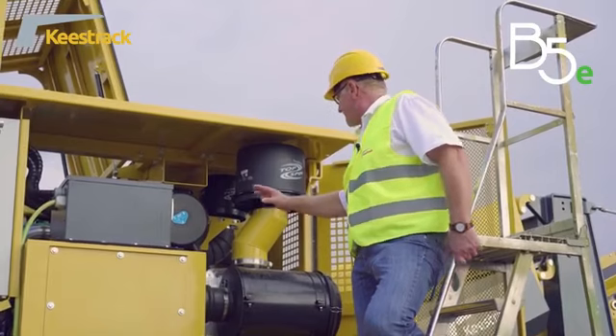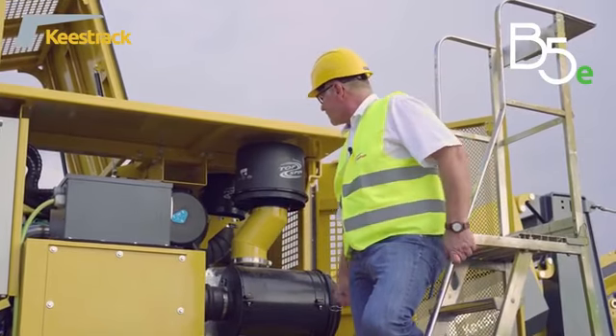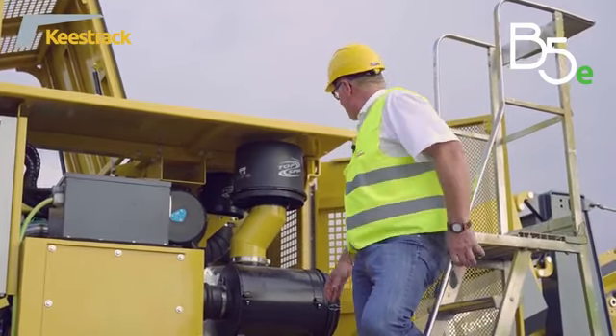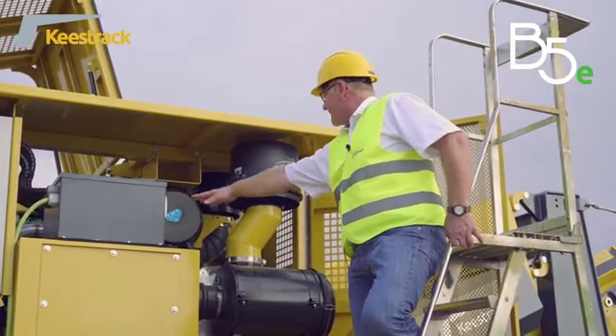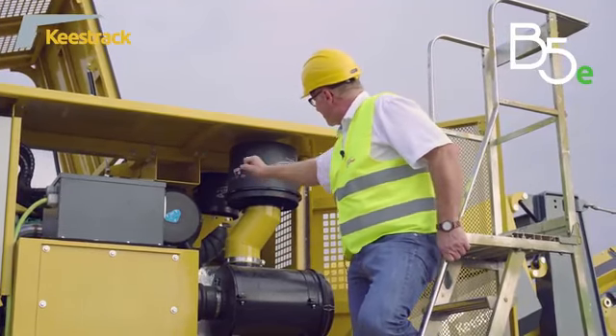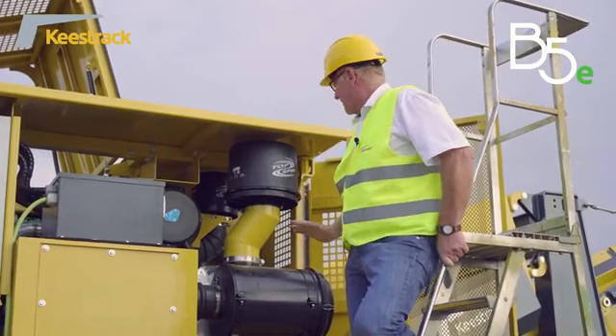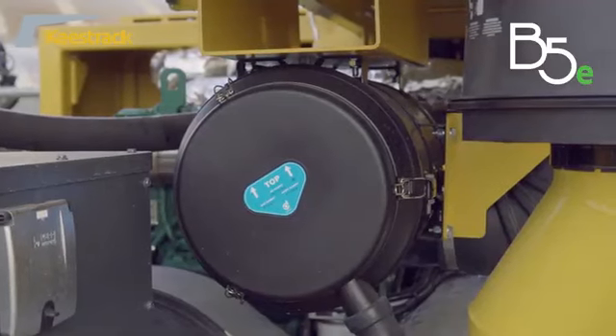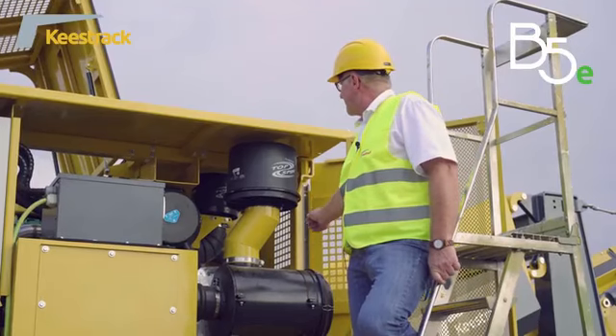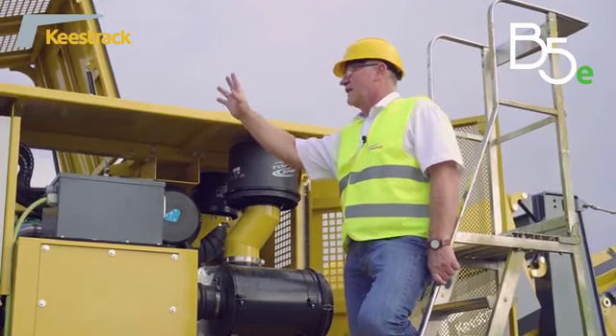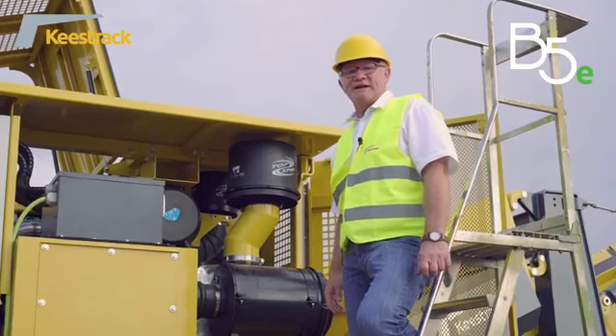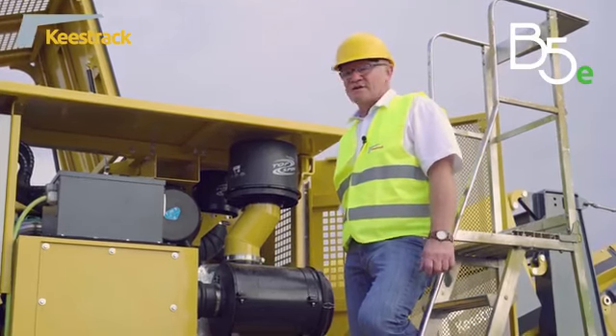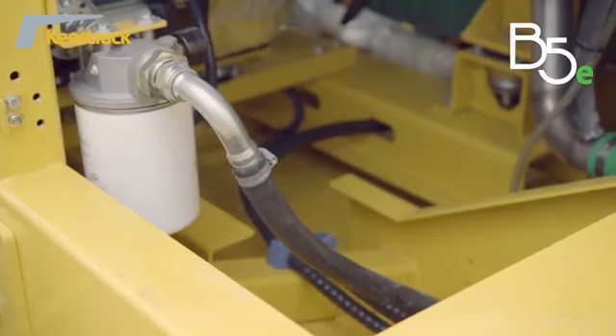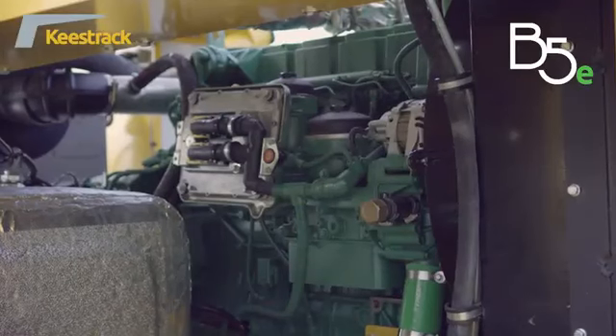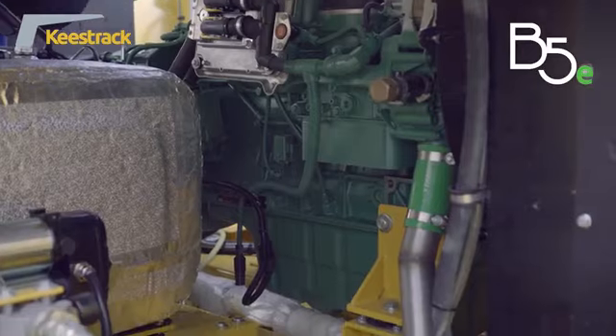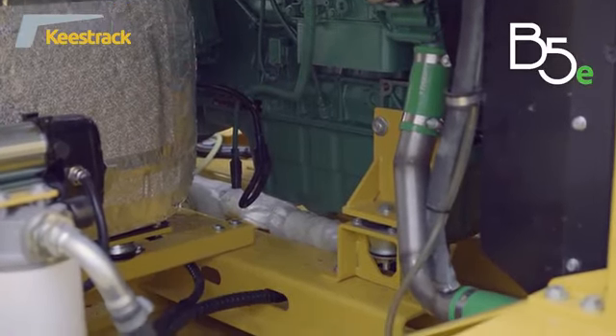The alternator has its own air suction system for cooling of the alternator with a filter, which you can see here, and a separate filter for the diesel engine. All the filters are made in the same range, with doors which can be opened easily, for ease of service. So from this side we have access to the engine unit, the refueling pump, and to the filter of the refueling pump.